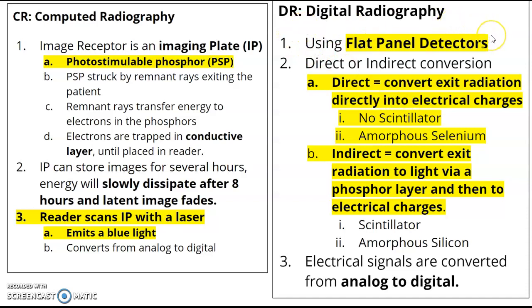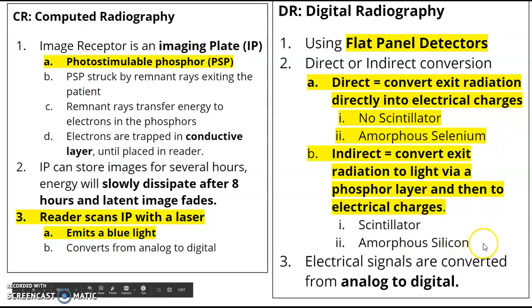Your DR is your flat panel detector. There's going to be direct versus indirect — one uses a scintillator, one doesn't. Your direct uses no scintillator; it goes directly to its conversion. And your electric signals are converted from analog to digital — that's the ADC conversion.